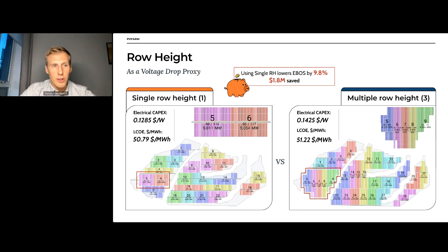A good example is the row height parameter, which might also be called block height. This, together with your inverter loading ratio or DC-AC ratio, approximately defines the block footprint. The block footprint and the electrical pattern you use - harness and combiner architecture versus trunk bus architecture - actually defines the cost of the low voltage system. On the left we locked in 2-height blocks, and on the right 5-6 height blocks, using a specific electrical pattern. We can see it was about 1.8 million saved, almost 10% in electrical cost - electrical cap is 13 cents versus 14 cents.